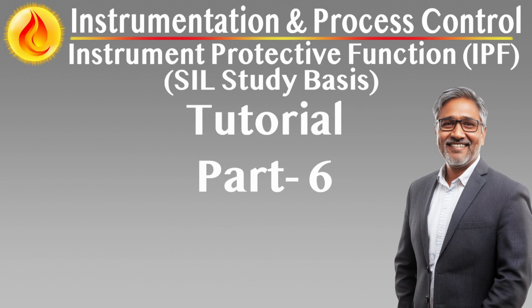Risk-based justification. Justification for each automatic MOS must demonstrate that the temporary loss of protection is either tolerable or offset by compensating measures. In SIL-rated functions, the impact of the MOS must be included in availability and PFDavg calculations where applicable. Access control and role separation. Only authorized maintenance personnel may activate an automatic MOS, typically via secure engineering interface or key-operated switch. Operations must have visibility but not control unless explicitly approved.